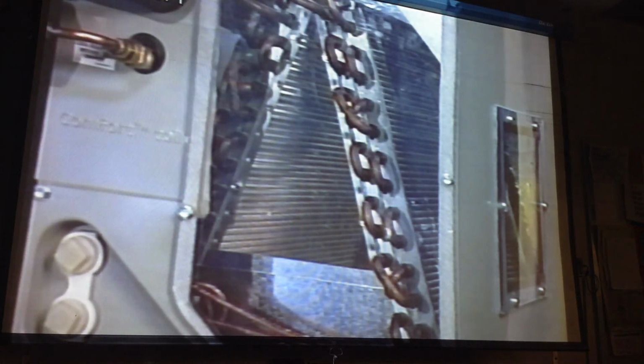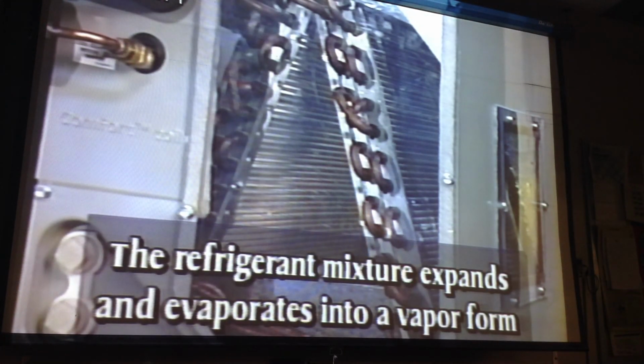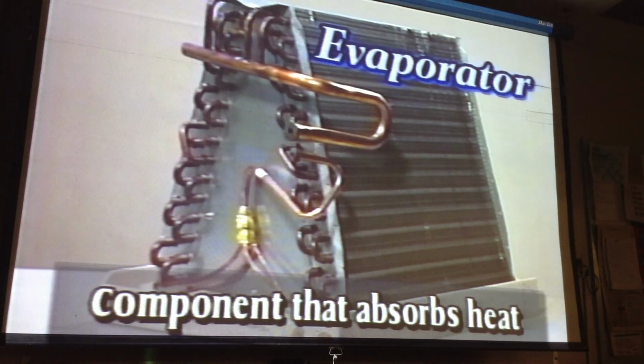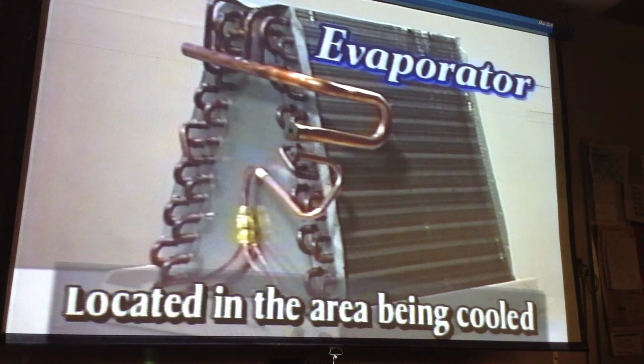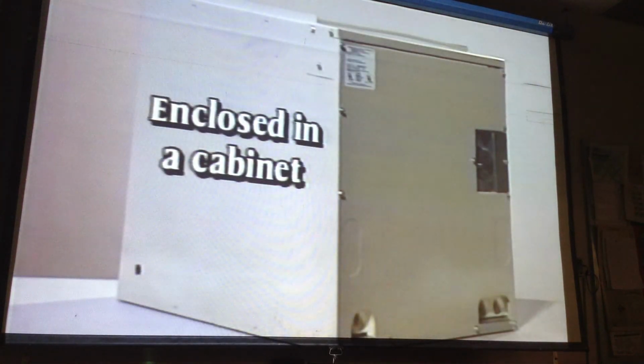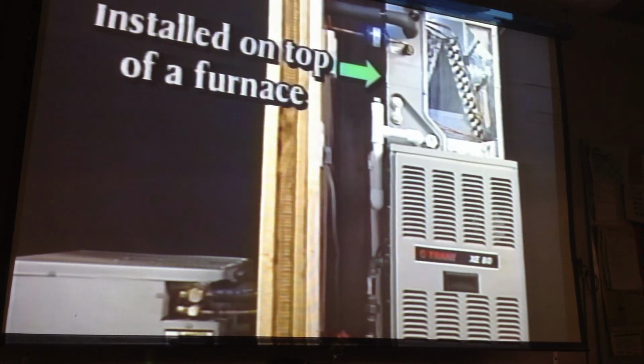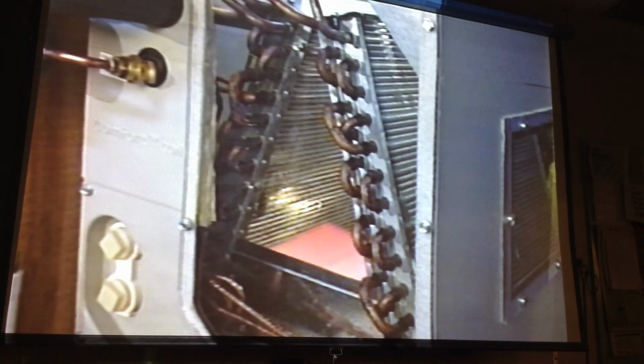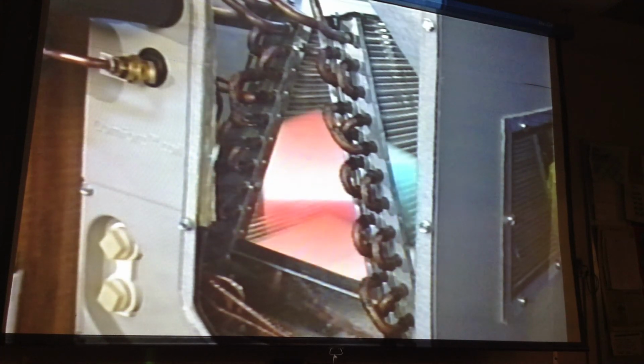Passes through the evaporator, it expands and evaporates into a vapor form. The evaporator is the component of the cycle that absorbs heat and is commonly located in the area being cooled. It is enclosed in a cabinet and will typically be installed on top of a furnace. A fan or blower moves air across the coil and creates the cooling effect.